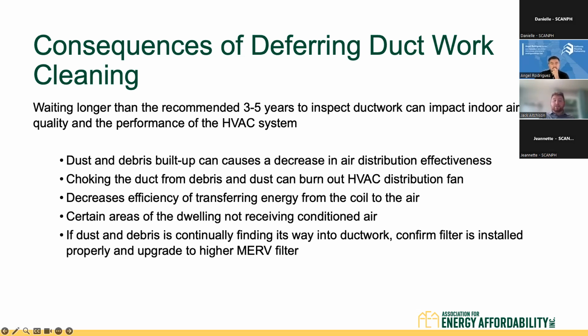Choking the duct from debris and dust can burn out the HVAC distribution fan. Again, these fans are designed to pull air through the coil and then push air through the ductwork. If we have a lot of gunk and a lot of stuff in the duct, that's going to result in sort of a back pressure on the fan, and that fan is going to have to work harder. It's going to burn out more frequently. Decreases efficiency of transferring energy from the coil to the air. Similar to the air filter, if we have a lot of back pressure from the duct because there's material in the ductwork, what's going to happen is our airflow over the coil is going to be reduced beyond what the spec or the design of the system is, and that's going to really impact our efficiency of conditioning that air and then distributing that conditioned air.